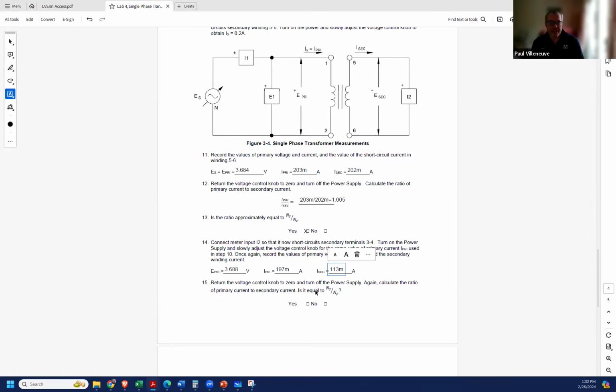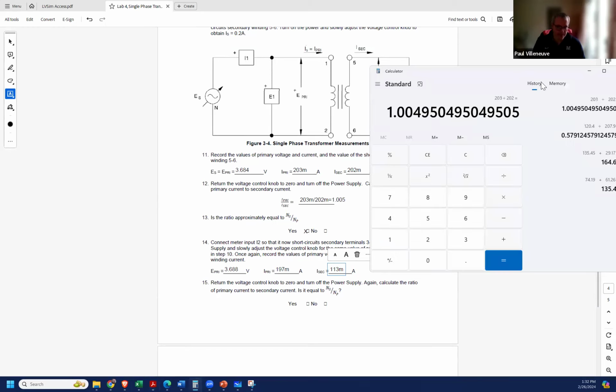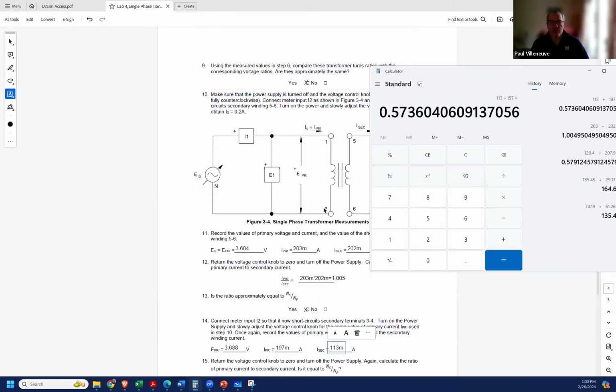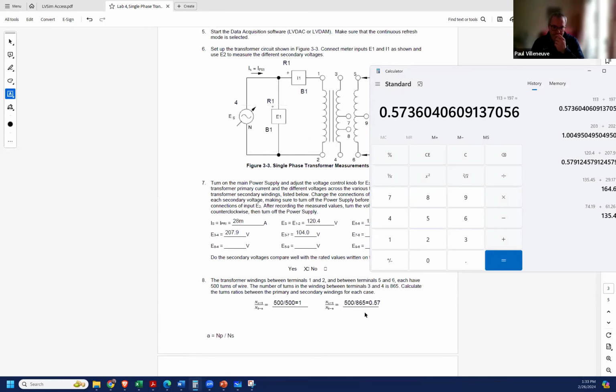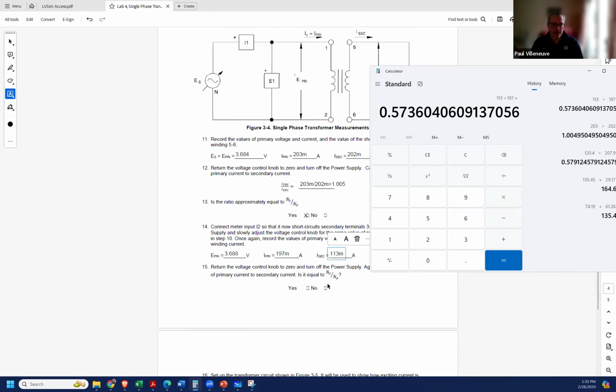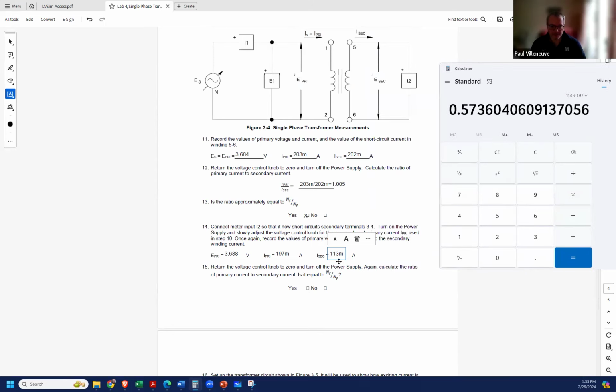So is this what we expect? Let's do the calculation first: 113 milli divided by 197 gives 0.573. The turns ratio for terminals 1,2 to 3,4 was 0.57, which matches. So this is the primary turns to the secondary turns, but over here, what I measured is the secondary current divided by the primary, and I ended up with that 0.57.